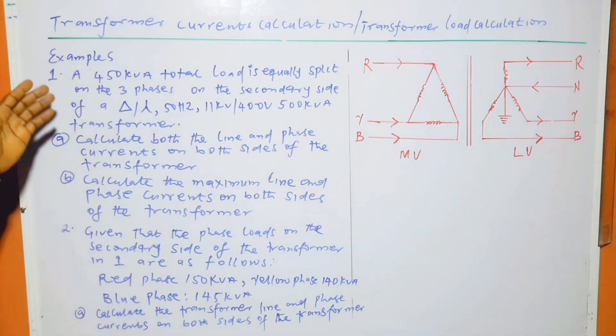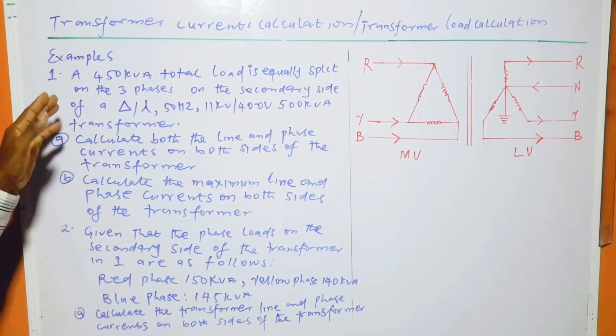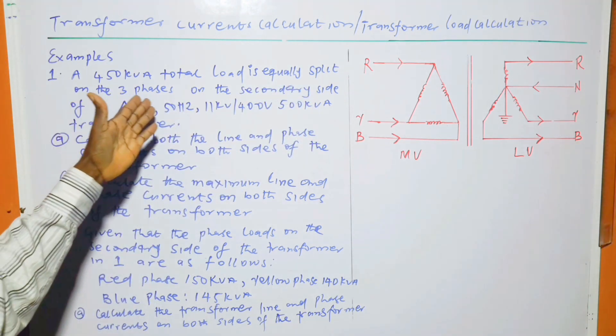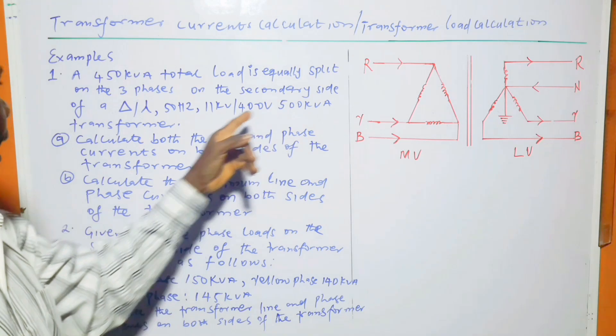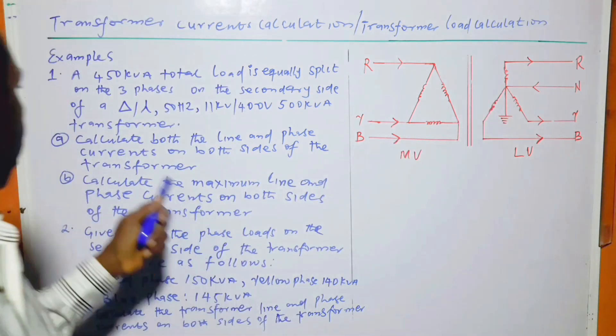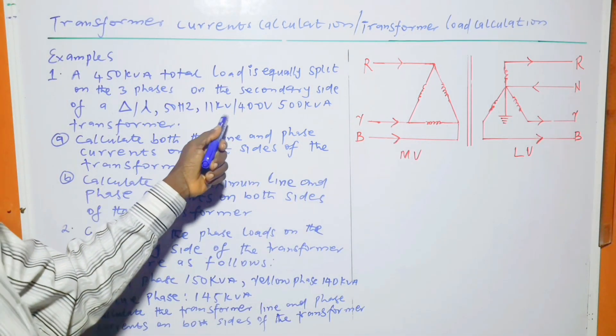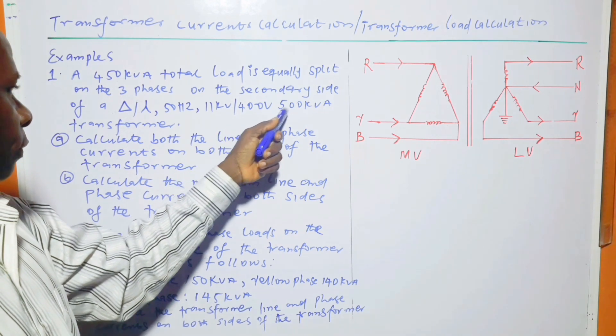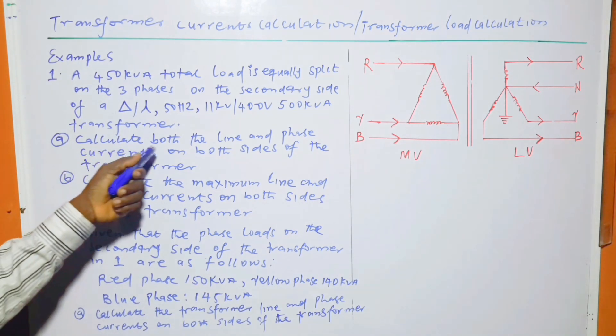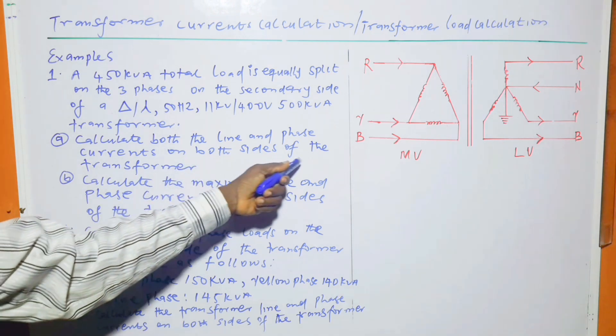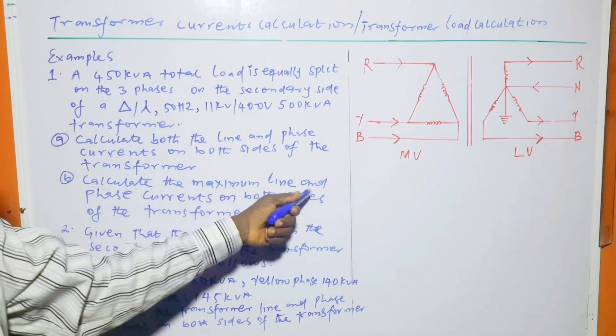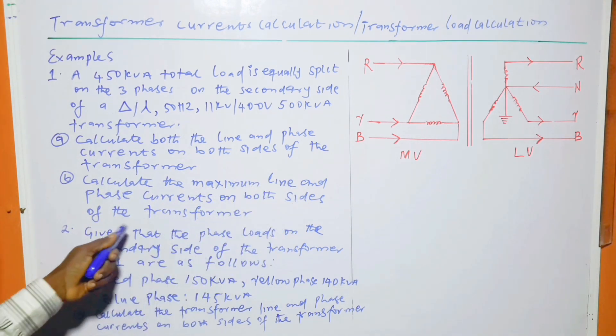Example one: a 450 kVA total load is equally split on the three phases on the secondary side of a delta-star, 11 kV / 400 V, 500 kVA transformer. The question asks to calculate both the line and phase currents on both sides of the transformer, and part B asks for the maximum line and phase currents on both sides of the transformer.